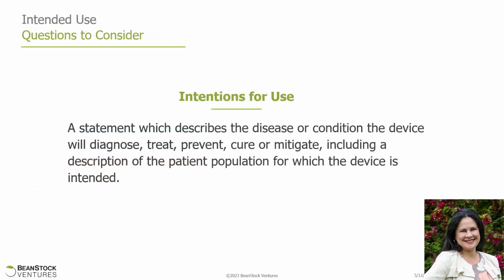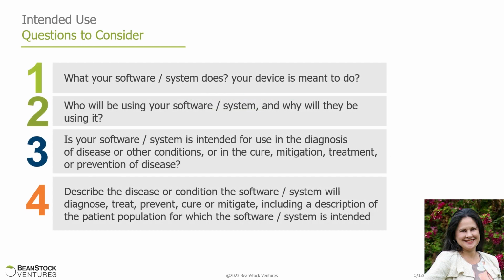Your intended use statement is a statement which describes the disease or condition the device will diagnose, treat, prevent, cure, or mitigate, including a description of the patient population for which the device is intended. We find sometimes it's helpful to ask our clients these 4 questions when creating their intended use statement. These are just questions for consideration that'll help you define your scope even further.